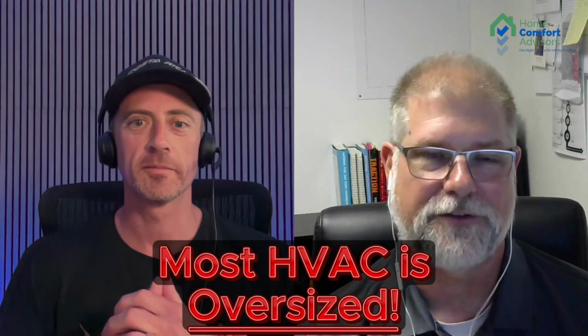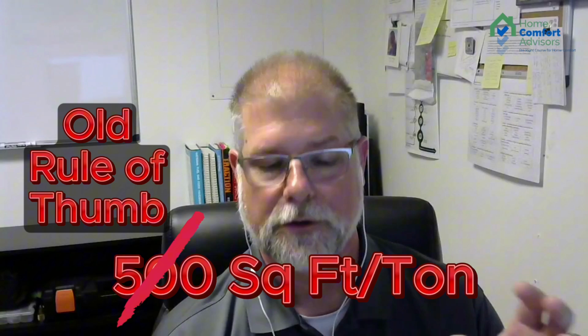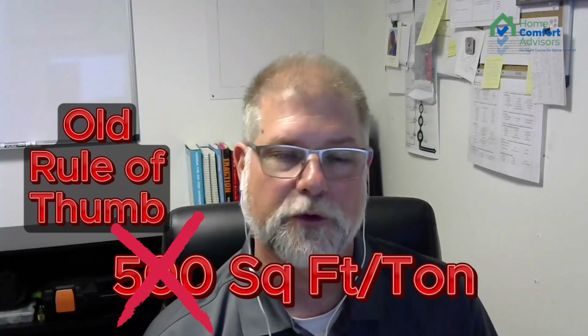There's another one. Going back to the equipment, most HVAC equipment is oversized. And we've been using rules of thumb that only apply to houses built in 1973. We still use them today in houses built in the last 15 years. And it has caused equipment to be drastically oversized. So unless you live in a house that was built in 1973 and it has had no updates whatsoever, if someone comes in and they use some rule of thumb like 500 square feet per ton, your HVAC equipment is likely going to be oversized.